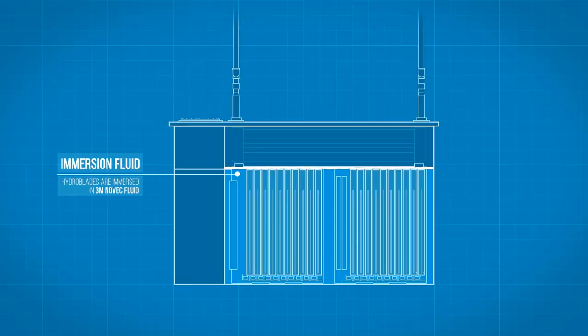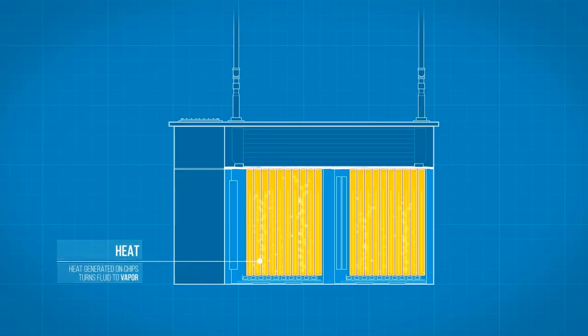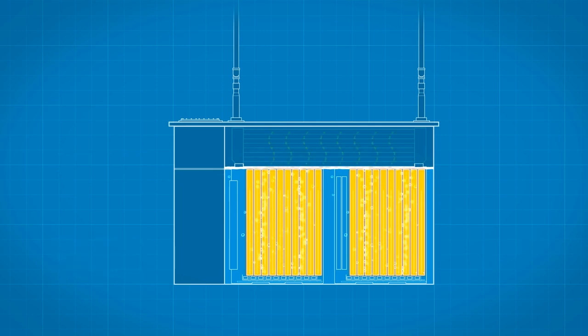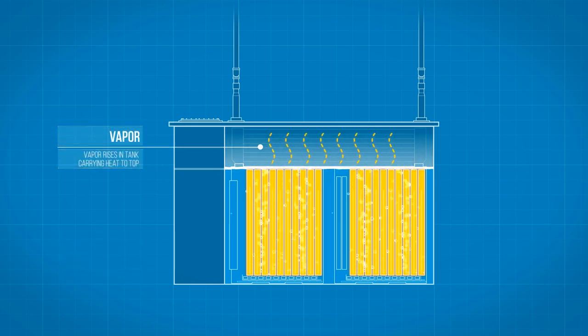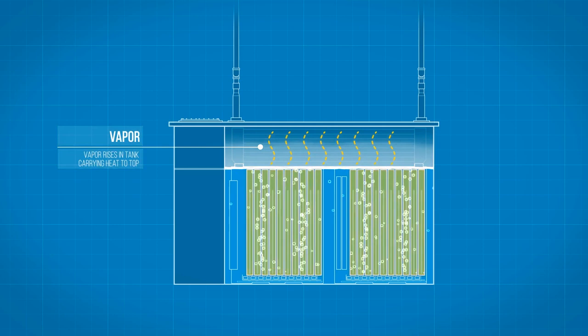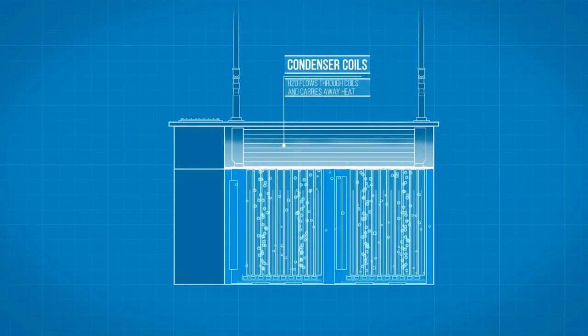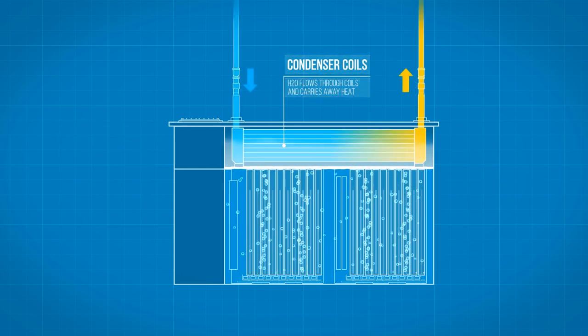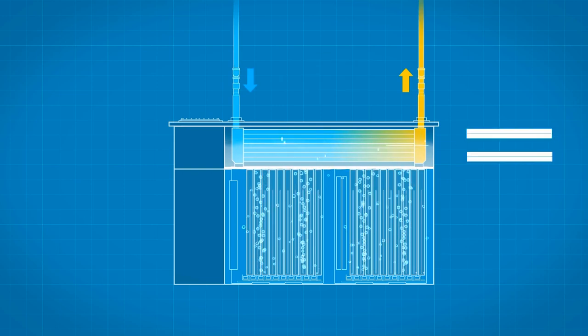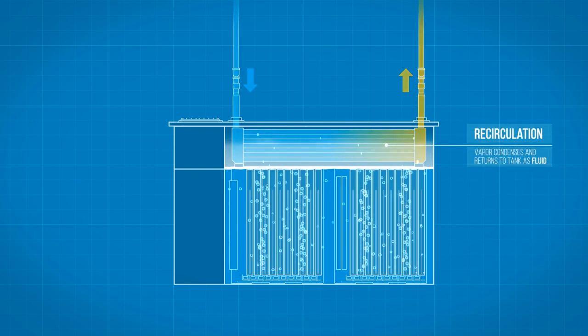As we start to power up and run the workloads on the server, those chips get really hot. That fluid then absorbs that heat thermally, and it transforms into a second phase, which is a vapor phase. That vapor phase then rises up naturally, and we have cooling coils on the inside of the hydropod, which circulate warm water, 90 degrees Fahrenheit or higher, and in some cases over 100 degrees, so we're not having to do any chilling of fluids, making it extremely efficient.